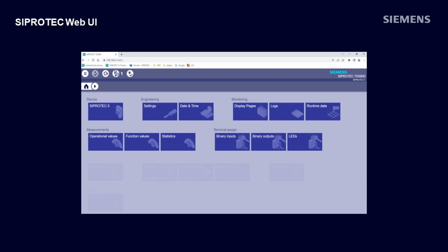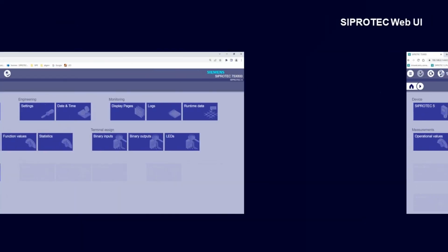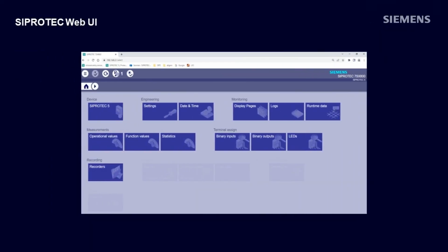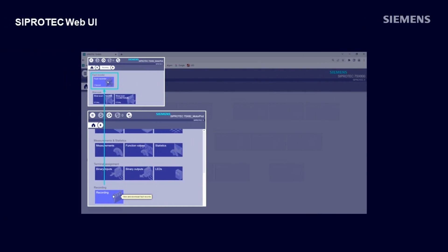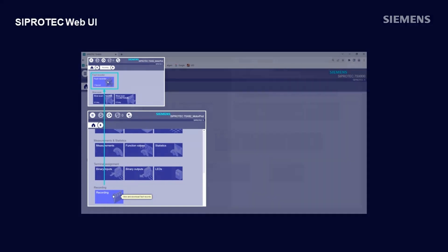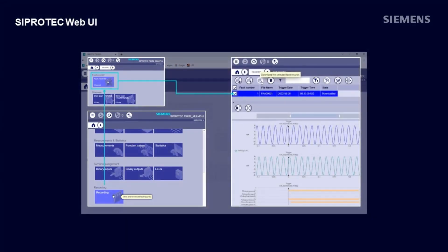The tile recorders brings us to the various recorders of SIPROTEC 5. When we click on recording, we see a tile for the fault recorder and for slow scan recorders. Clicking on the fault recorder tile opens the view for fault recorders. Here you get automatically a list of all records in the device. You can show a selected fault record clicking on the symbol with the eye directly in this window. You can trigger a fault record with the second icon with the plus sign, and you can download the marked fault records to your PC.